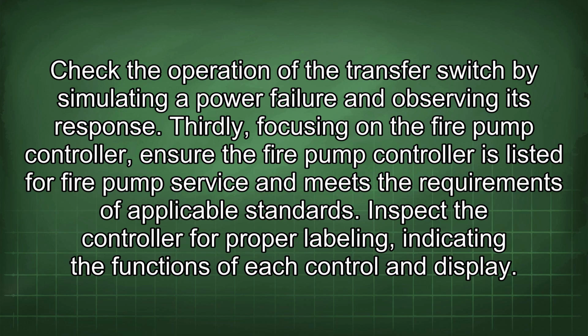Check the operation of the transfer switch by simulating a power failure and observing its response. Thirdly, focusing on the fire pump controller, ensure the fire pump controller is listed for fire pump service and meets the requirements of applicable standards. Inspect the controller for proper labeling indicating the functions of each control and display.